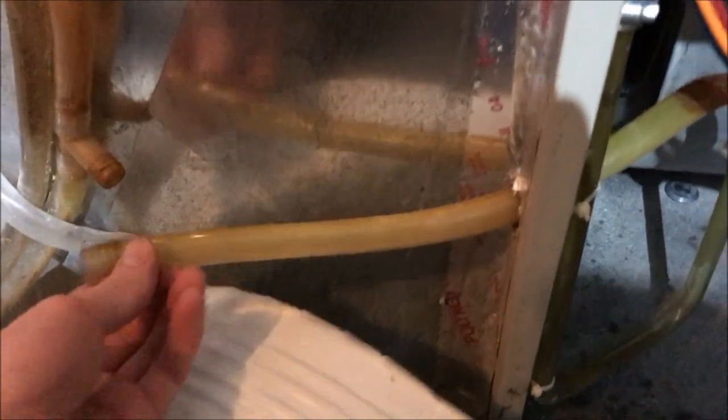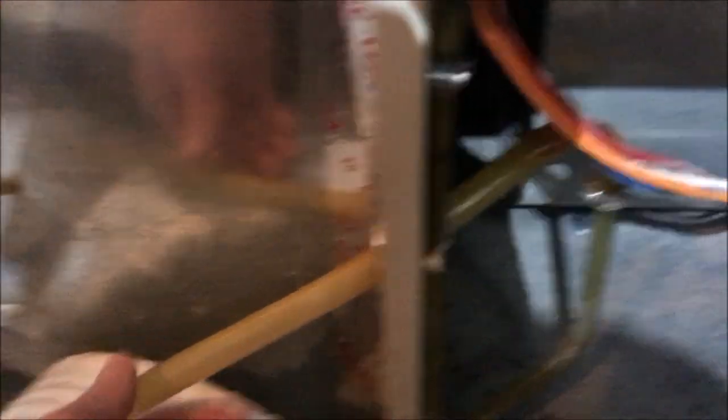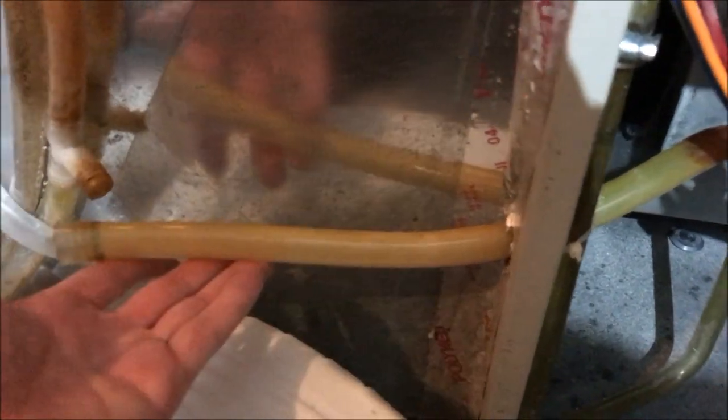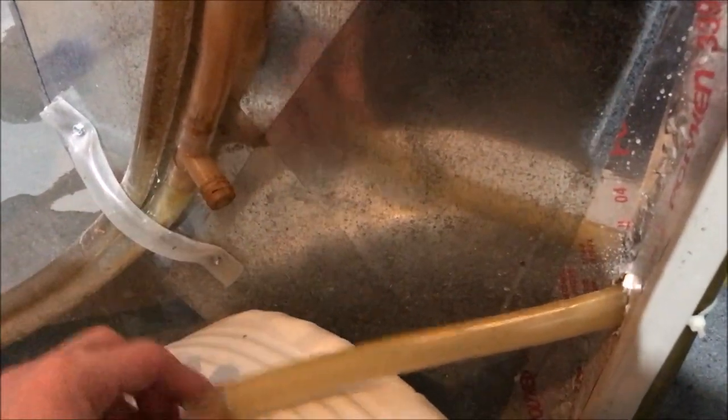Another preventative measure in this entire business is making sure your lines are clear. There's no mold growing in them or anything like that. Bacteria. You can see there's stuff growing in mine. I blew them out and I had a bunch of crud that came out. So that wasn't helping my situation at all. Also this p-trap needs to be adjusted. You can see that it's connecting to this T right here. But it's putting a bend in the pipe right. This should, you know this is kind of at an angle down. Generally they're pretty horizontal. You want to make sure there's no bends in the middle of your pipe that would cause any type of condensation to work its way back. I'm actually going to replace this hose with a longer one which will allow the T feeding to come about right here. It'll just give me more of a downward angle. Therefore I don't have to really worry about water going back in there and having this problem happen to you again.